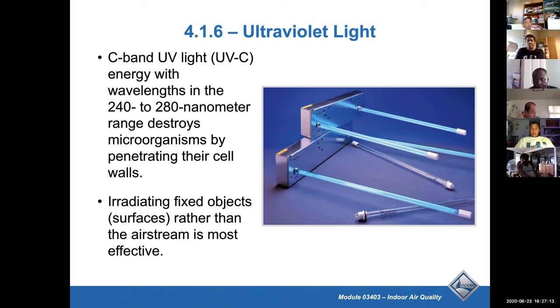Pat? Yes. Question? Is it true that they're using the plasma right now? They're using plasma, yes, instead of the UV light. And they're using another one called ion. It basically puts ions in the air. And I don't know how effective it is. I know the ion hardly needs any maintenance. Because UV lights are only good for 1 year to 2 years, and then you got to change them. They burn out. And they cost anywhere between $30 to $100 a piece, depending on the size. So that's one thing about UV lights. The ion and the plasma one, I think, have very low maintenance. I'll have to look into that.